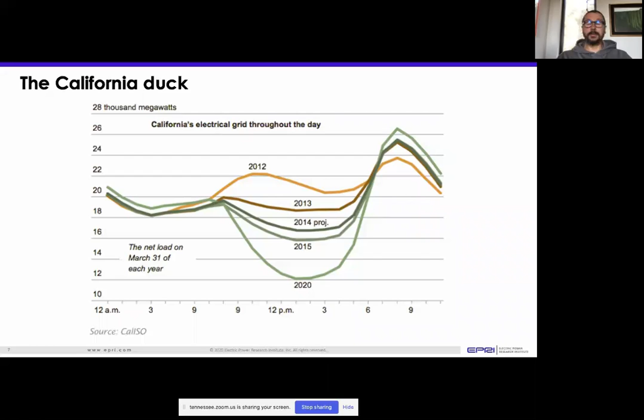So this is just on the micro scale — this is what generates a duck. These are actually compressor speeds for a number of customers in a project we're doing here at EPRI. We're monitoring the power of a number of customers' heat pump compressor speeds, and you can see the same thing: a morning peak, not much happening in the middle of the day, and then an afternoon peak again.